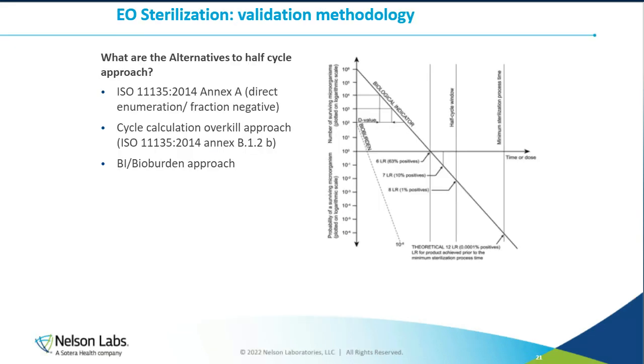So I have covered the PCD calibration. Now I mentioned that all of you that are familiar with ethylene oxide sterilization have probably been using the half cycle approach most of the time. But what would be the alternative that we can use instead of this half cycle approach? So the ISO 11135 Annex A is allowing to use alternative approaches such as direct enumeration or fraction negative.